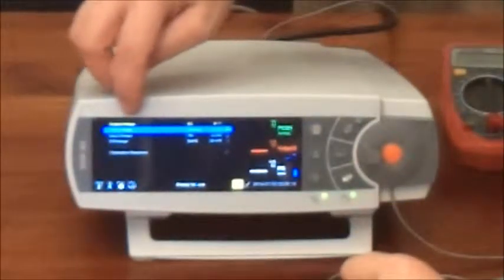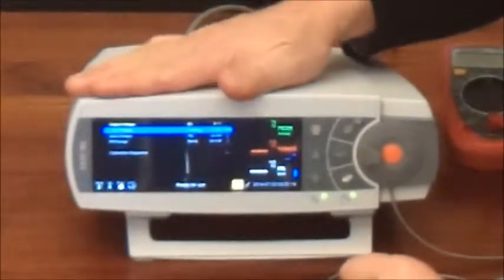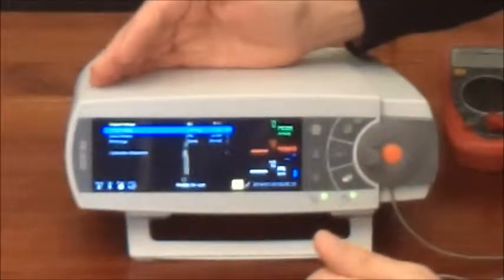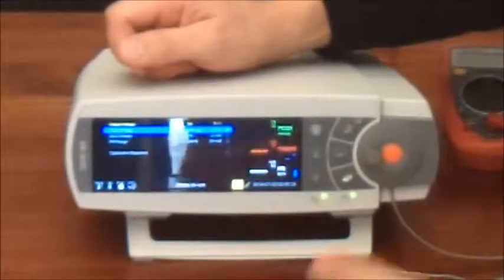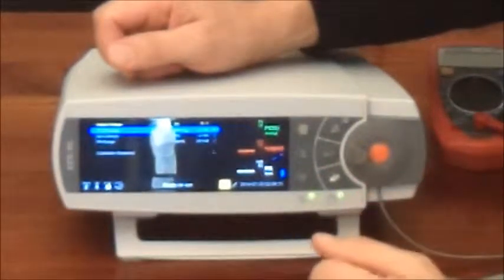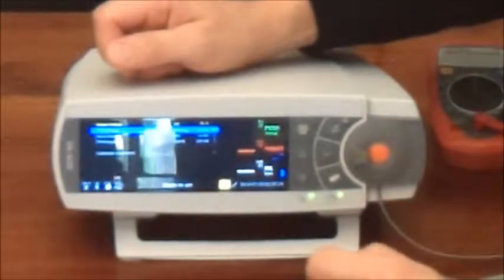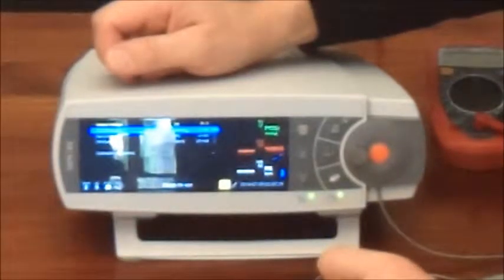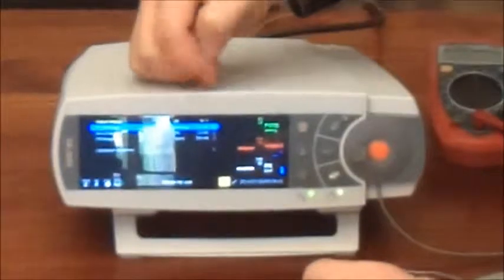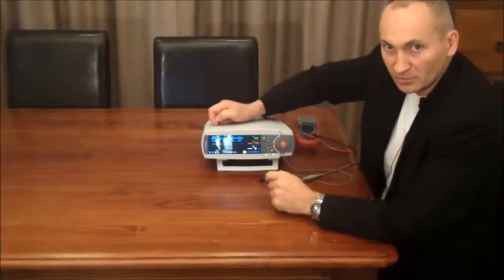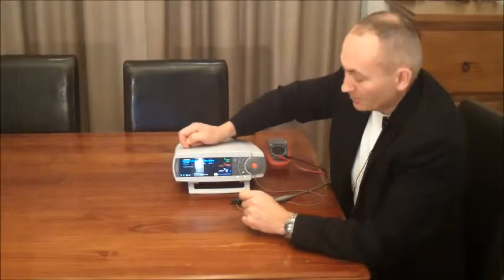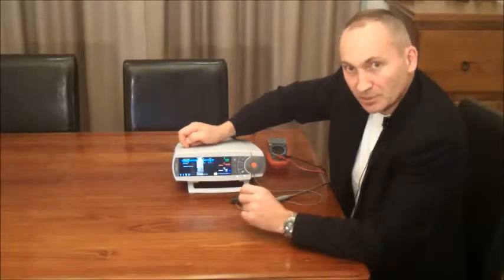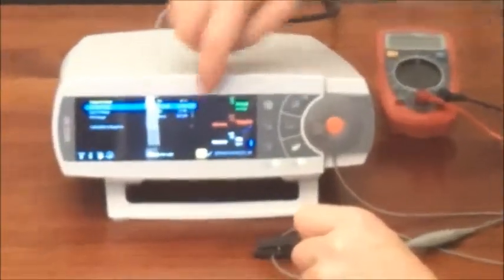Now at the top in yellow it says output voltage, volts zero to one. Obviously it can go higher than one volt, but this is going to give you a table to tell you what zero means on the back of the machine and what one means. So let's say the CO2 signal is at 50 millimeters of mercury—we want to know what that means in terms of voltage out the back of the machine. In this case, zero to one volt means zero to 100 millimeters of mercury, so 50 millimeters of mercury is going to be 0.5 volts.